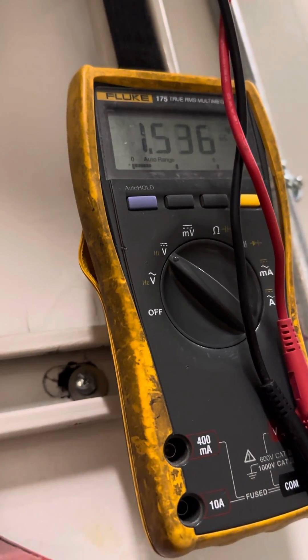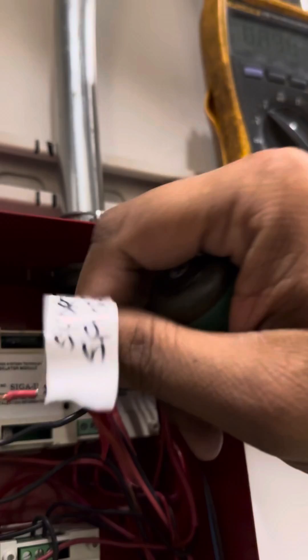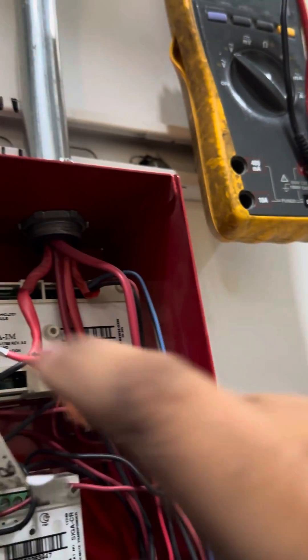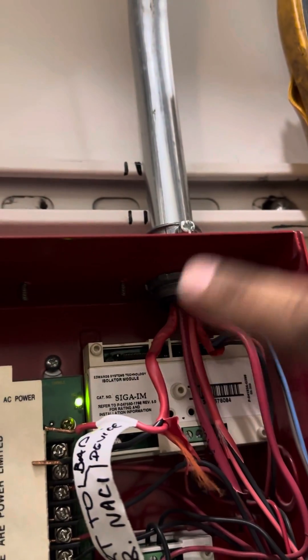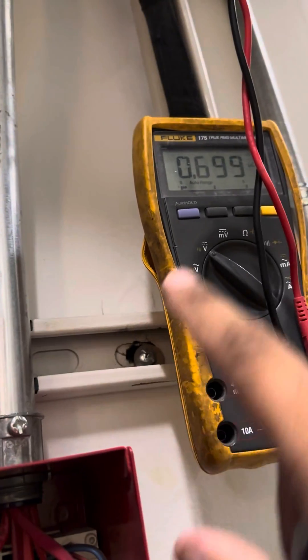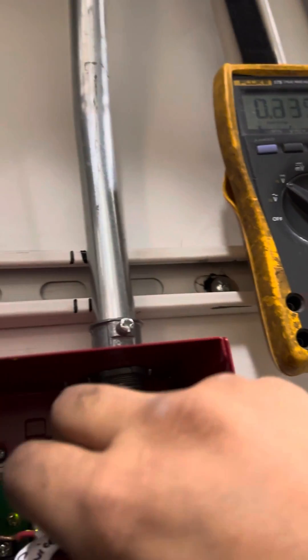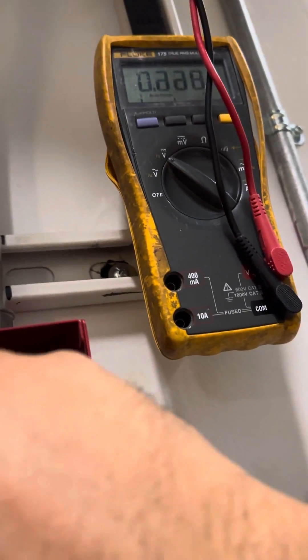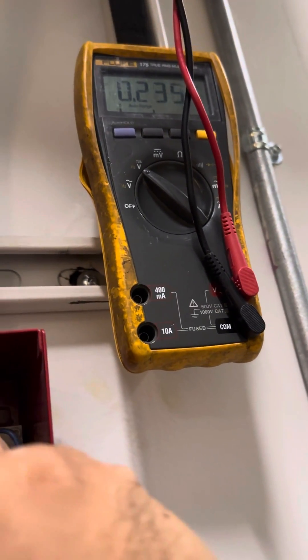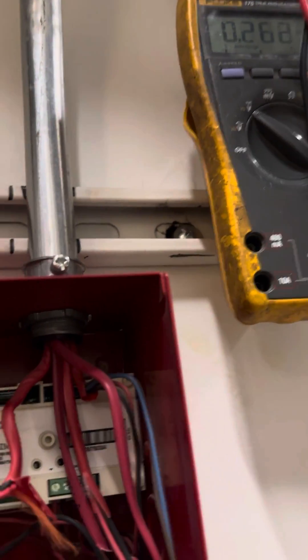So that's an indicative issue that the strobe circuit is shorted out to the speaker and it's back feeding all the way up to the amplifier. And on the Edwards panel it will just report as a ground fault and intermittent. So I hope that helps you.